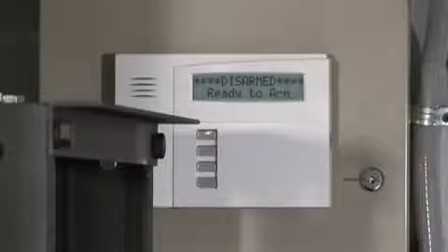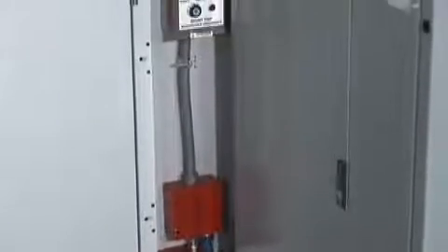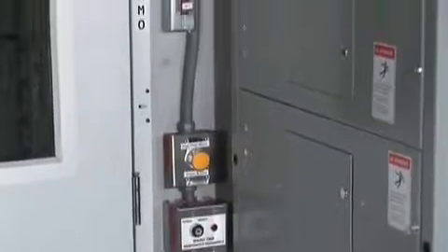As we step out once more into the vestibule area, we see the hookups bringing water into the container. On the other side, we find the electrical switch panel. And inside the panel, we trace the cable inputs into the breaker section and get to see some of the current transformers used in gathering our PUE measurements. All in all, there are many additional support systems required to satisfy the safety and occupancy requirements of the container, including emergency off buttons, fresh air supply, fire detection, fire suppression, smoke dampers, and much more.